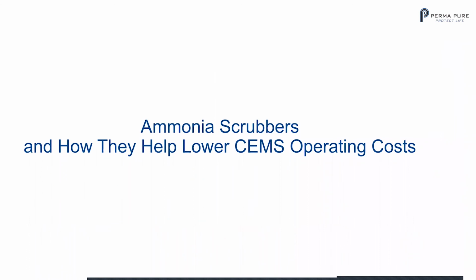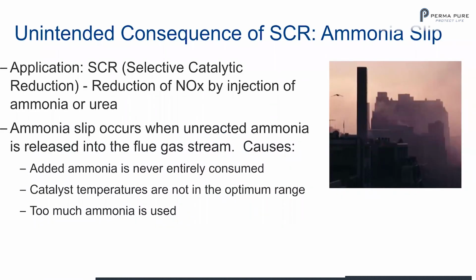The next and last part is how ammonia scrubbers can help lower CEMS operating costs. And what we're talking about here is installing ammonia scrubbers with coolers, okay? So as we know, the unintended consequence of SCR is ammonia slip, where you use the selective injection of ammonia to reduce the NOx emissions. The slip occurs when unreacted ammonia is released into the flue gas stream. The causes are that added ammonia is never entirely consumed, the catalyst temperatures are not in the optimum range, or too much ammonia is used.